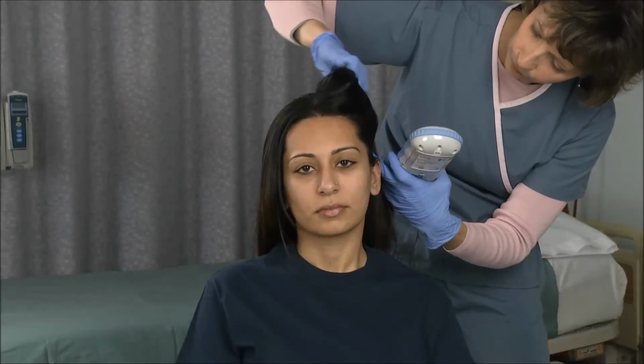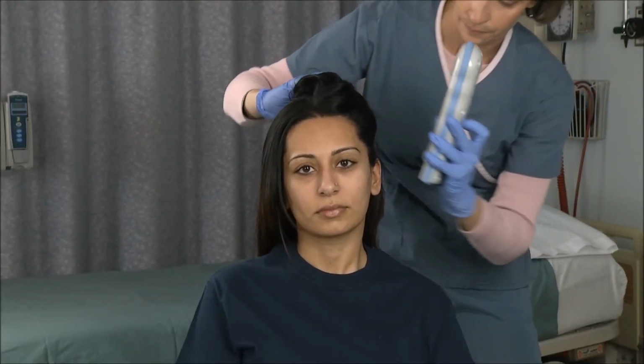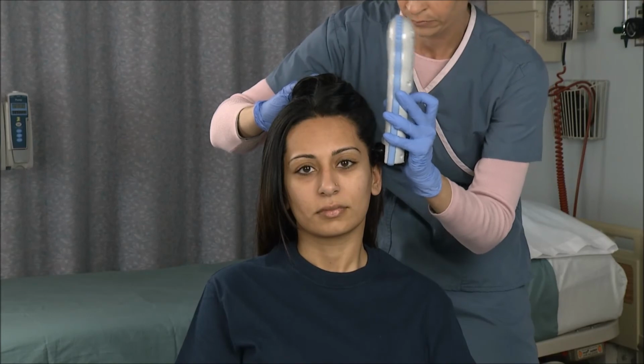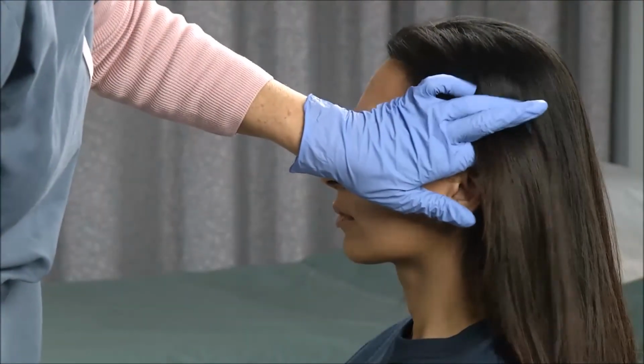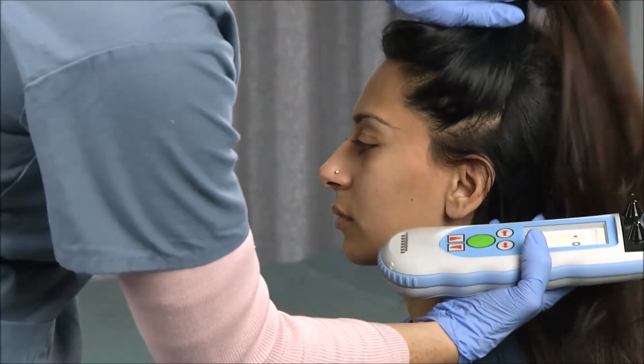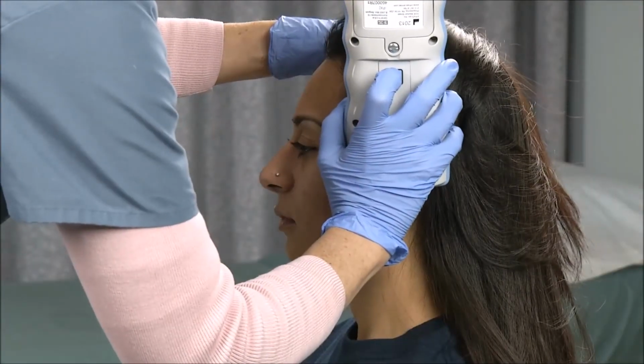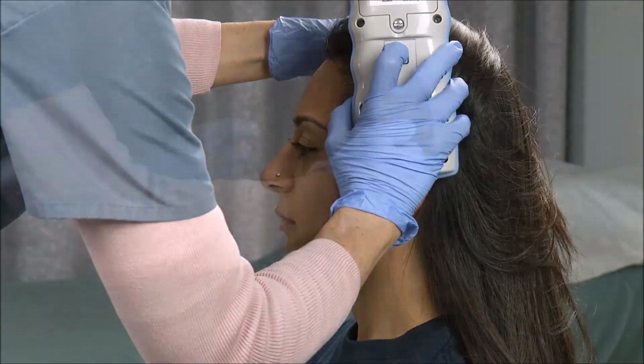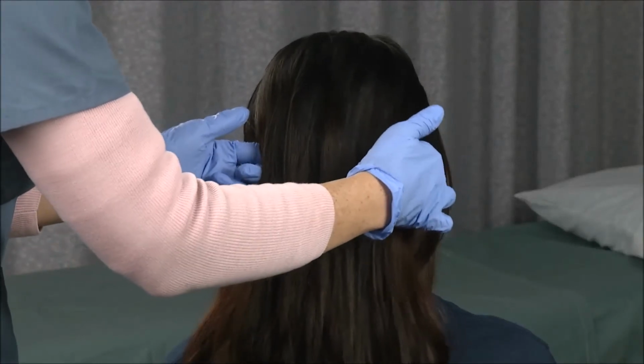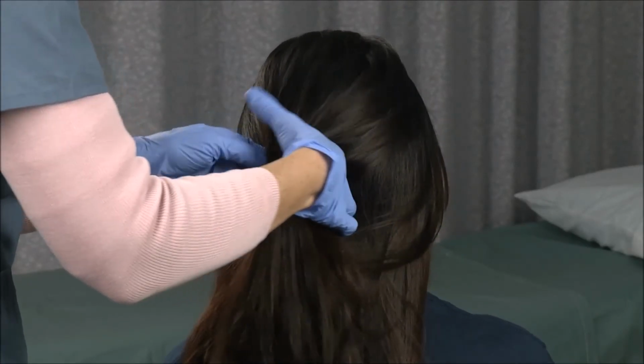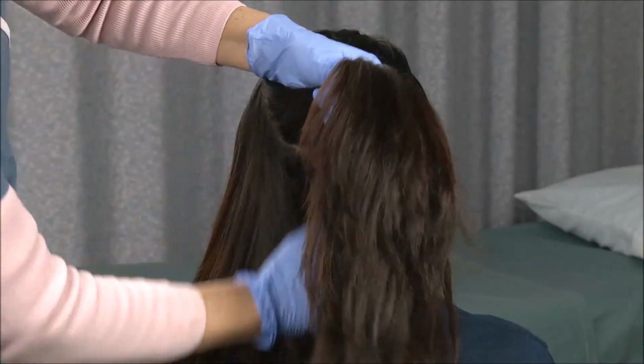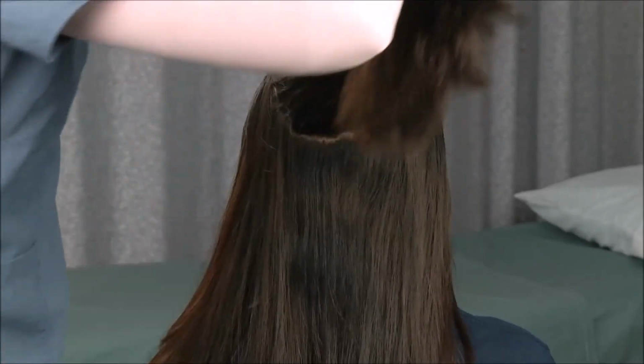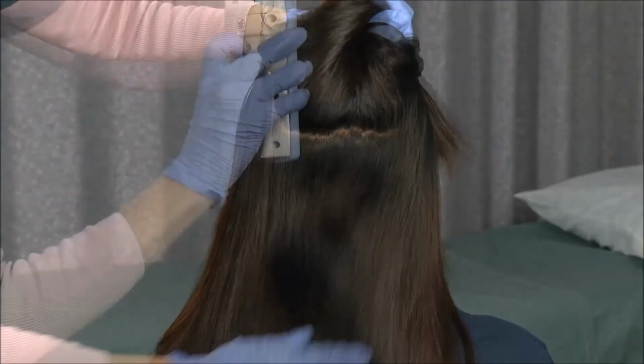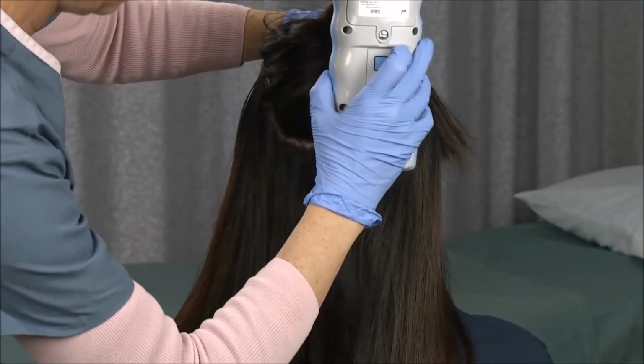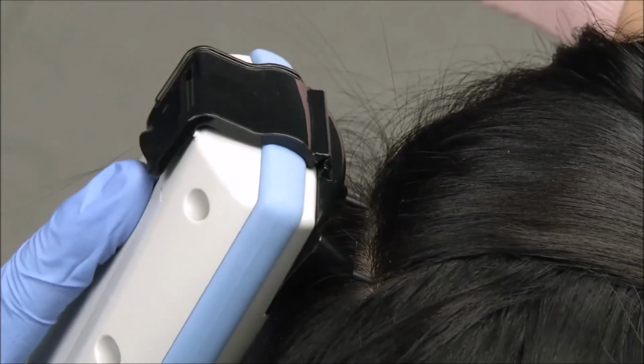In certain cultures, like in the Indian subcontinent and the Middle East, hair can be extremely long and dark. This type of hair can be managed by carefully separating the hair over the measurement location with the fingers and using the wiggle technique. Use both hands when making the parts, particularly for the occipital measurement, as it makes it easier to gather all the hair and take both measurements at the same time. Because dark hair or skin pigment can challenge the unit's light source, maintaining direct contact with the scalp throughout each measurement is essential.